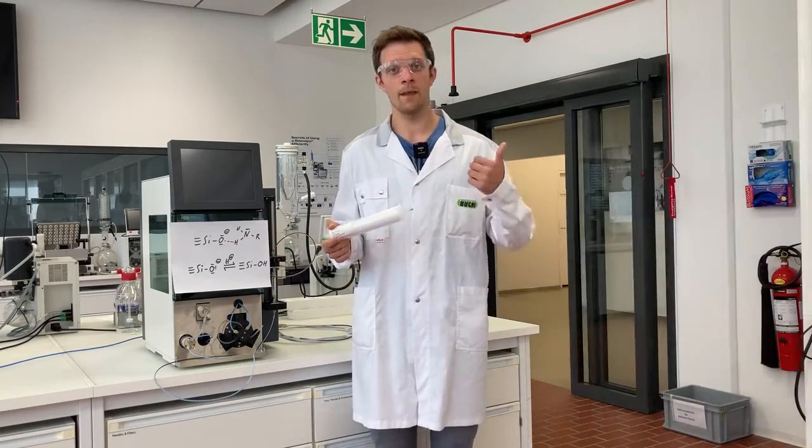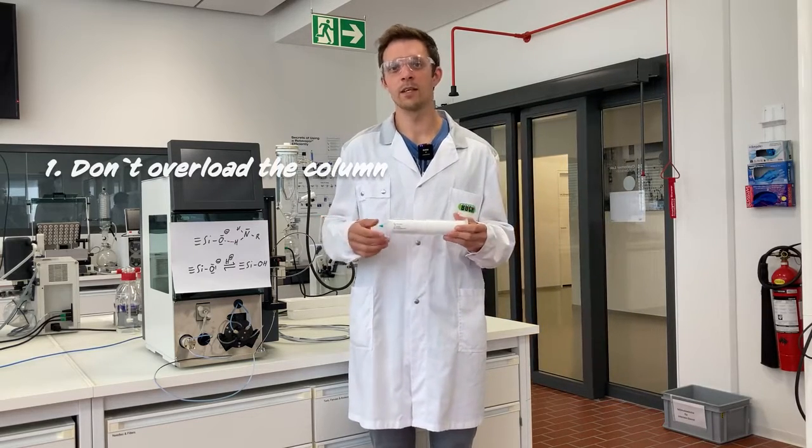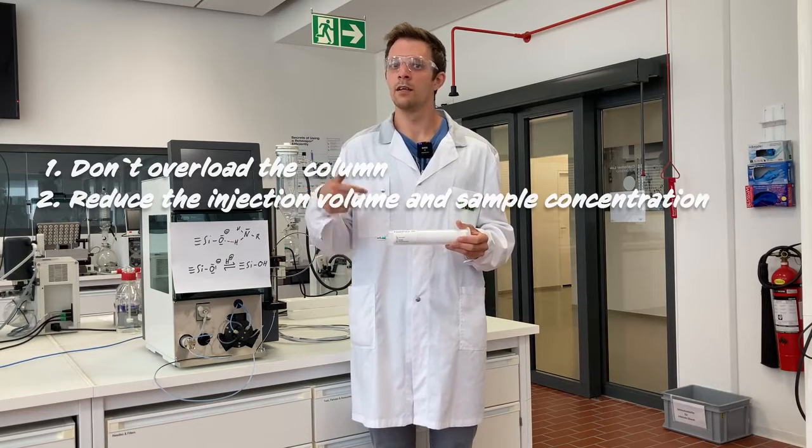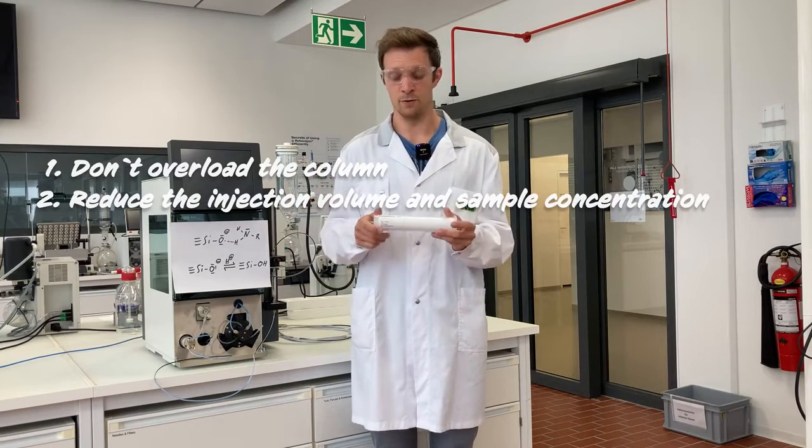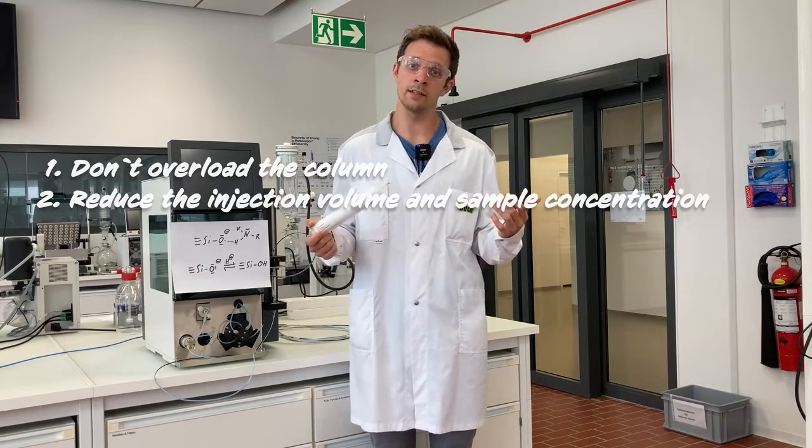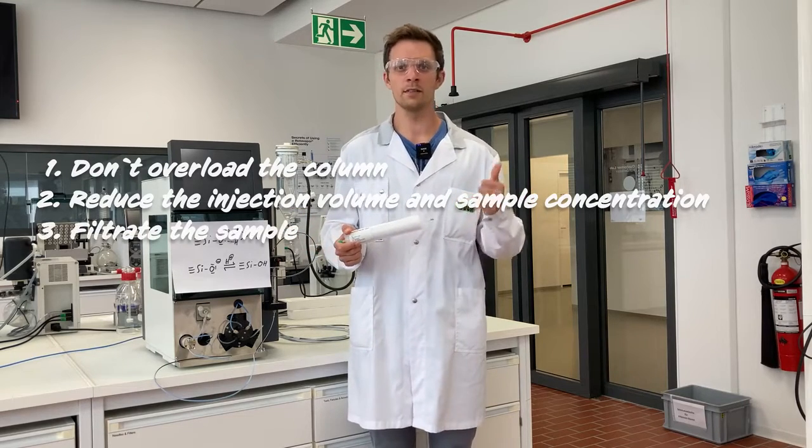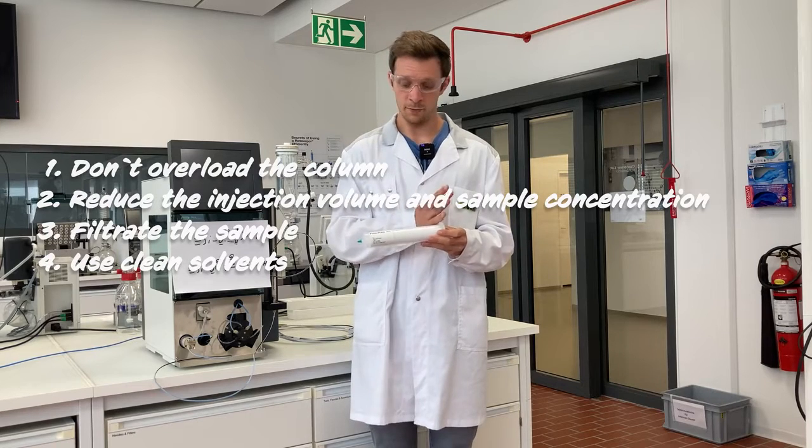And summarized, again, do not overload your column or cartridge. Reduce the injection volume of your sample or reduce the sample concentration of your sample solution. And regarding packing bed deformation, filtrate your sample, use clean solvents, or reduce the flow rate to decrease the pressure to avoid peak fronting.